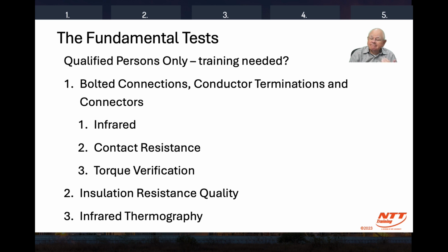Insulation resistance testing, we've got to be sure we're consistent there, that everybody's doing the spot reading test for 60 seconds. We're correcting for temperature as needed. If we're doing something like a polarization index, does whoever's doing that test know how to interpret those readings? And for infrared thermography, of course, that takes special training, right? We become certified as an infrared thermographer and produce a report on our equipment. But all of those three vital areas, bolted connections with torque connections and connectors, insulation resistance testing as number 2, and infrared thermography, are all recommended.